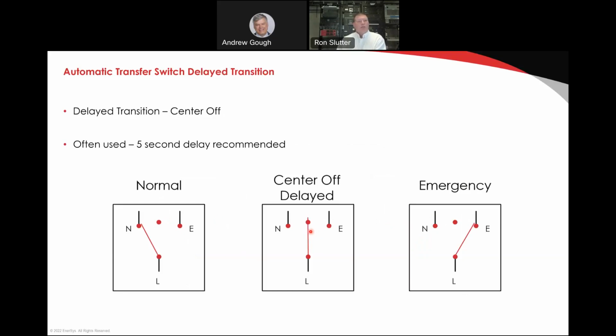So let's move on to another standard design of an ATS, which is delayed transition. So delayed transition has two mechanisms, and it actually moves from normal to the center off position. As you can see here, this is called center off because we can go to this point and stop. So it's very different. It's physically different than open transition. So how do you get this? You have to order it. You have to order the ATS designed for delayed transition. If you do not do that, then you're not going to get it because this is completely physically different. You cannot program open transition ATSs to be delayed.